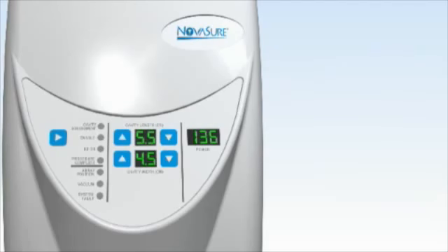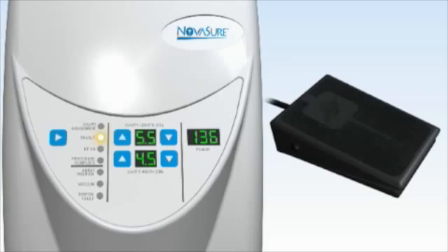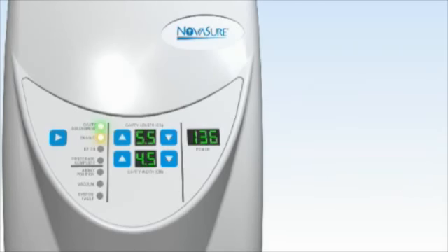The NovaSure RF controller can be operated in two different modes, automatic mode and semi-automatic mode. Please note, in some Model 9 RF controllers, a vacuum pre-check occurs automatically prior to the initiation of the ablation cycle. The vacuum LED will flash and an audible tone will be heard for up to 10 seconds during the vacuum pre-check. To operate the system in the automatic mode, press the Enable button prior to beginning the cavity integrity assessment. Begin the cavity integrity assessment procedure by stepping on the foot pedal once. Upon successful completion of the cavity integrity assessment, the ablation cycle will start automatically.